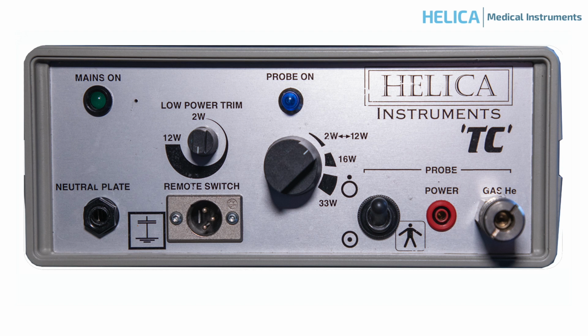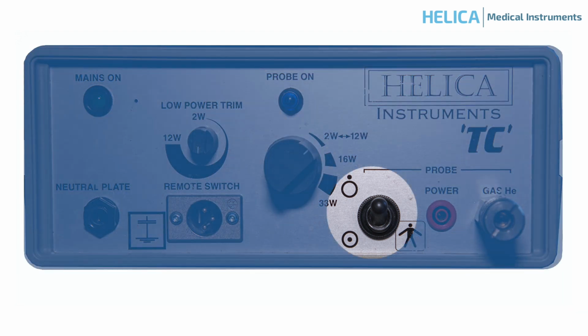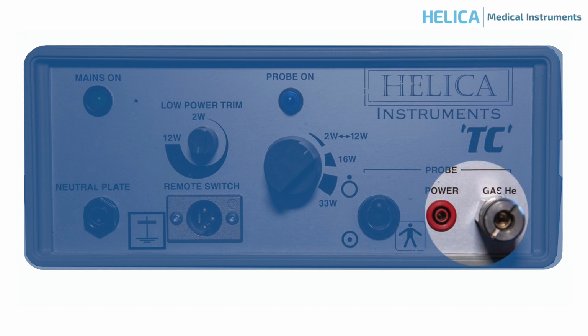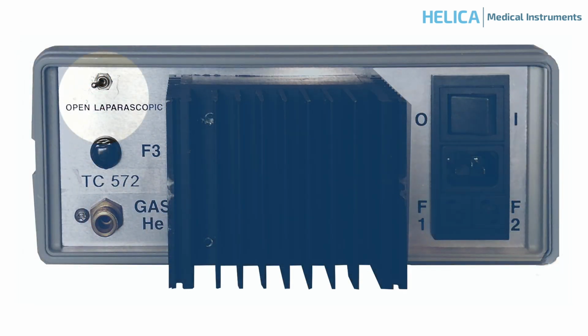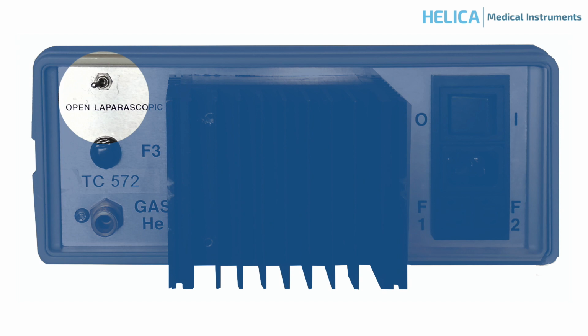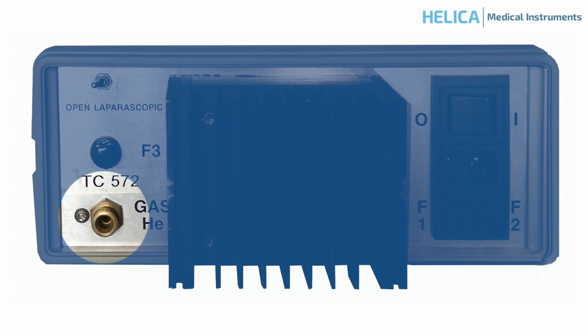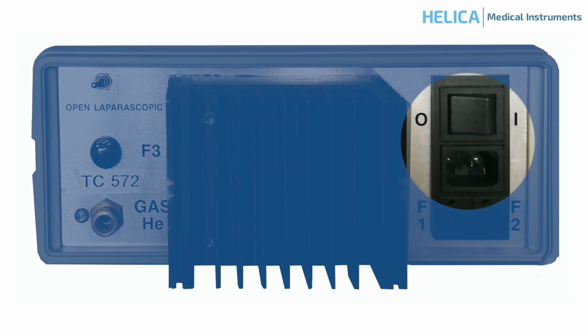Below and to the right, there's an on-off control switch. This should be used when changing probes. Furthest to the right are 2 probe ports. One is for the electrical power supply and the other for the helium gas. At the back of the machine on the left, there's a procedure switch which indicates laparoscopy or open. The open position is used for open surgery. Below this switch is the helium gas entry port. Furthest to the right is the main power socket and the mains power switch.